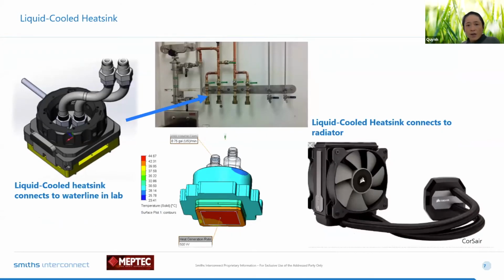So another option to address high power device testing is to use liquid cooling. In the lid you see right here, we designed it so that it can connect to the water line available in the lab facility. For this one, the simulation we have is for 500 watts, and with that, the case temperature is less than 85 degrees C. The fluid is from the water line, so you cannot change the temperature or the flow. For this example, it's around 0.75 gallon per minute.